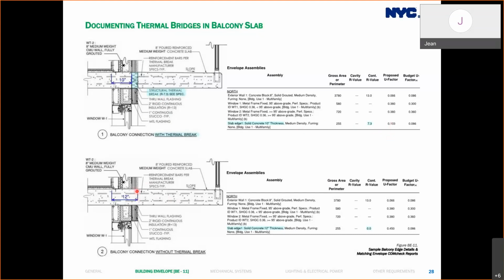But if you don't have any structural thermal break, you can only report this area as basically a 12-inch thick wall if you look from the outside of the building. So you say solid concrete 12 inches thick, and there is no insulation whatsoever. So your U factor gets much worse than before without the structural thermal break. And I recommend you check out, this is BE 11, our how-to guide BE4, which prescribes how continuous insulation in balconies and parapets mitigates the linear thermal bridges.